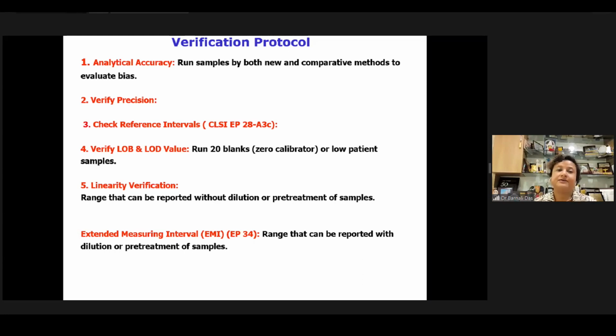When we start any new test or any new instrument, the verification protocol should minimally consist of analytical accuracy: run samples by both the new method and a comparative or gold standard method to evaluate the bias. Then verify the precision, then check the reference interval according to CLSI EP28-A3c. I am in the CLSI standardization committee, and I am also part of the ICMR reference interval advisory board. There are many differences in opinion when we compare direct and indirect reference intervals. Among diagnosticians there is still much variation in opinion on how to establish the reference interval. Should we go for the direct method or the indirect method?